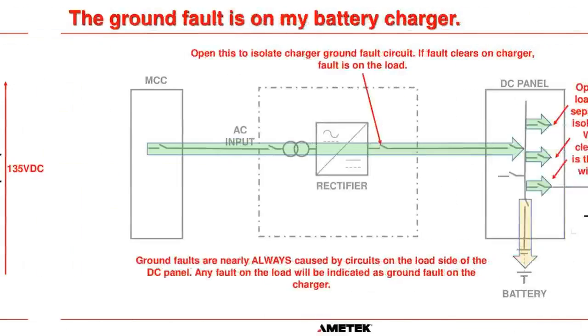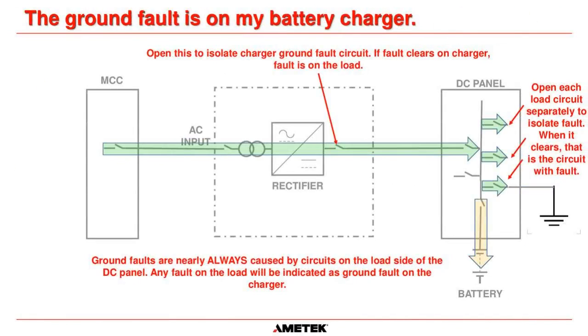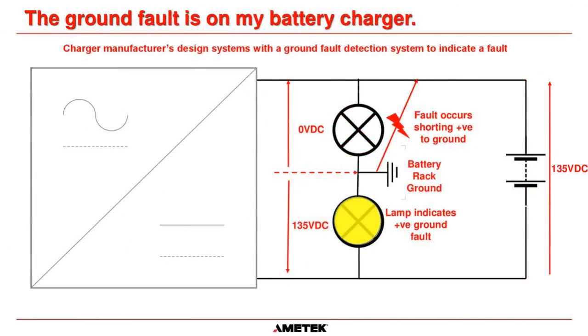Very, very basic ground fault detection circuit. Okay. Obviously, the problem with having 2 lamps in series is eventually incandescent lamps burn out, and you can get false readings and can cause problems. So most charger manufacturers now use electronic comparator circuits inside their system. This still uses a potential divider resistance circuit that will cause the battery voltage to be half and half. So hopefully that explains why the ground fault is not always on the charger.